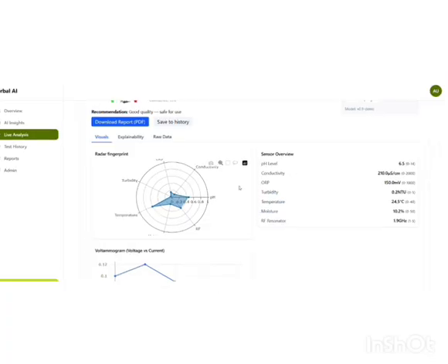If you are conducting this experiment on an unknown sample, even that unknown sample has to pass all the sensors and it generates a fingerprint. Now that newly generated fingerprint is compared with the stored fingerprints. If any of the fingerprints is matched, we can say that this unknown sample has particular known characteristics and the user can know about that unknown sample well.